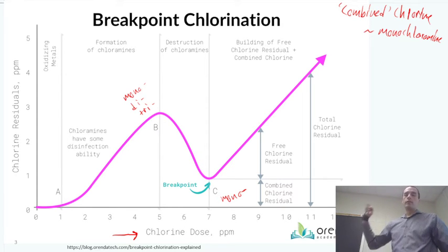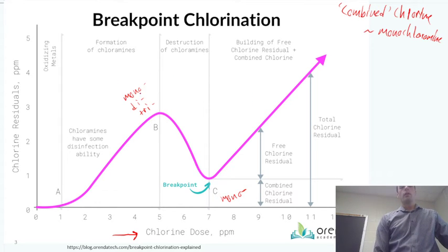Yeah, and now this can also sort of show you why, as we think about the presence of natural organic matter and how reactive that is, or the potential to form disinfection byproducts, if we did not have any control of the nitrogen, there's a whole lot of nitrogen there, then our dosing is going to be quite large here. So there's going to be more and more potential for disinfection byproducts if we're dealing with a whole lot of chlorine in the first place. So maybe if there was a step to be put in to reduce the nitrogen before we even got to that, that could help reduce the chlorine requirement.